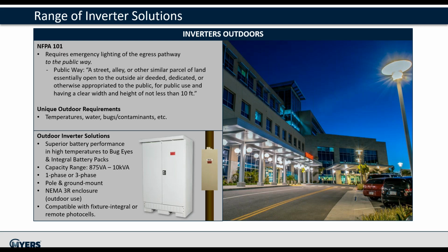This created a need for outdoor NEMA 3R systems with unique requirements due to temperatures, precipitation, debris, bugs, etc. Outdoor inverter systems have superior performance when compared to unit equipment or battery packs that would be placed in this harsh environment. Small power units are pole-mounted or pad-mounted and range from 875 VA single-phase to larger 10 kVA three-phase systems. Outdoor inverters are compatible with all outdoor fixture types, including integral or remote photocells.